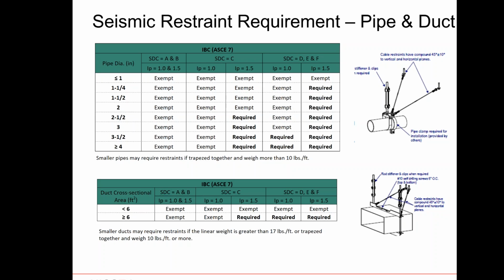For SDCs of D, E, and F, you can see that there's still a requirement for 1.0, anything that's 3.5 inches or larger. I'd love for someone to show me some 3.5 inch pipe, never seen one. And then for anything that's 1.25 inches and larger, for 1.5, you'll have a requirement to restrain.